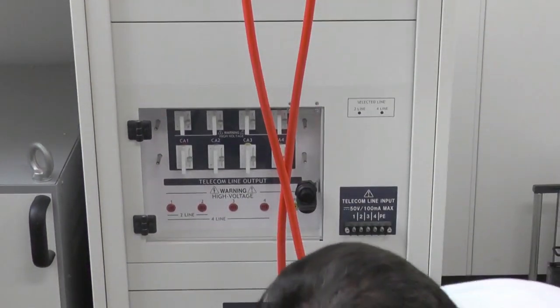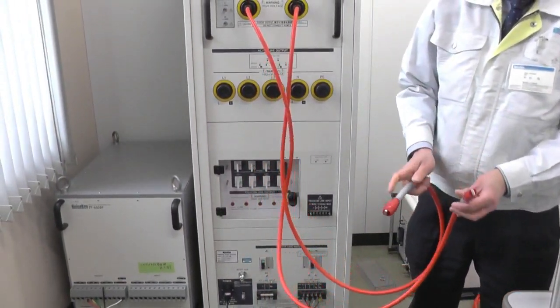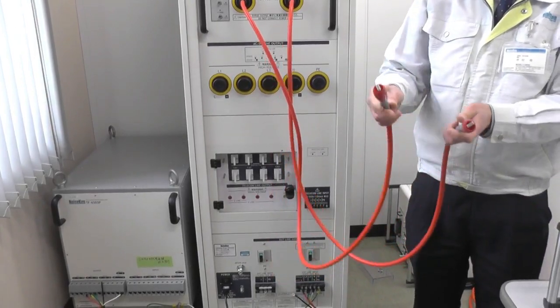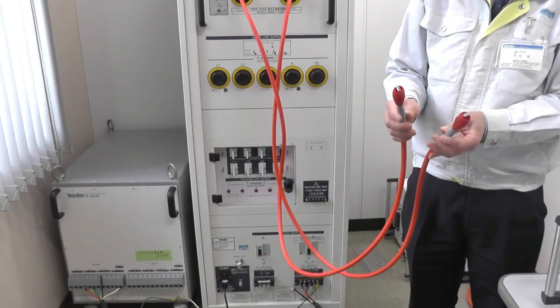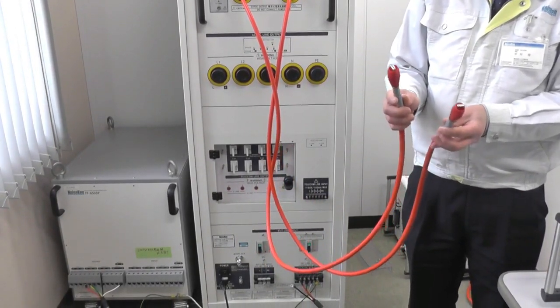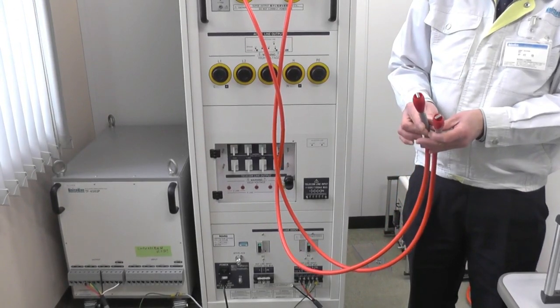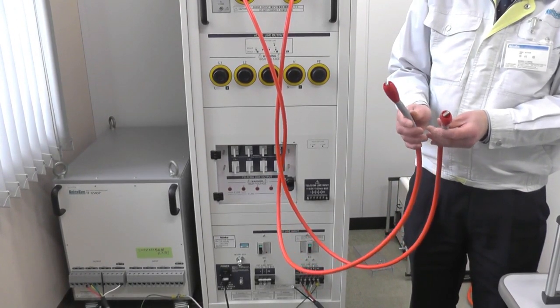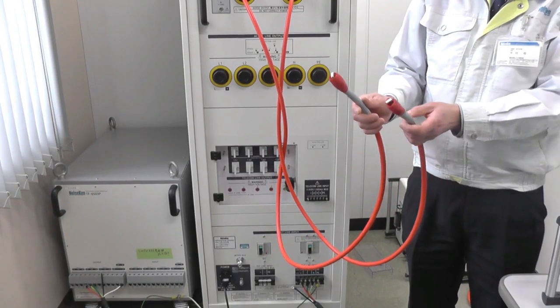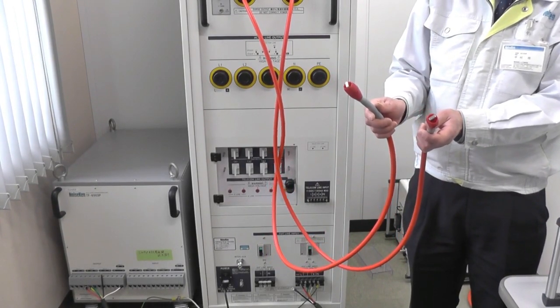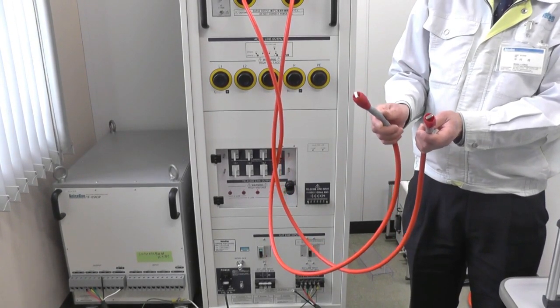Then you might want to connect the end of the surge output cable and inject the lightning surge. And please keep in mind not to connect the ends to AC-DC power sources, which might damage the inside of the simulator.